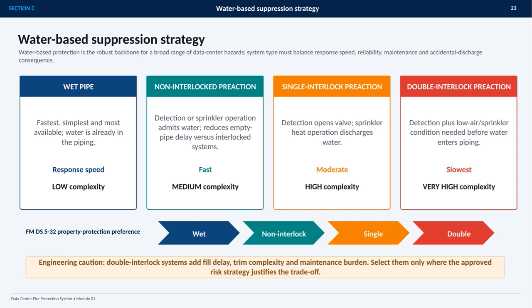Single interlock preaction adds another layer. Detection opens the valve, but sprinkler heat operation is still required before discharge. That makes response moderate and complexity high. Double interlock is the slowest and most complex. It requires both detection and a low air or sprinkler condition before water enters the piping.